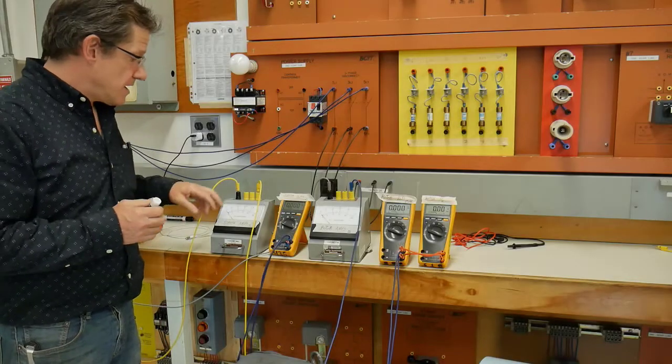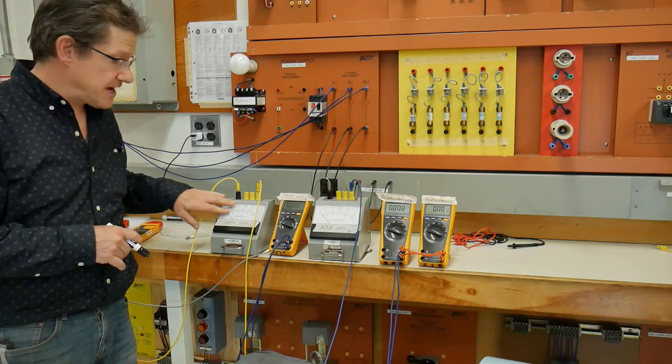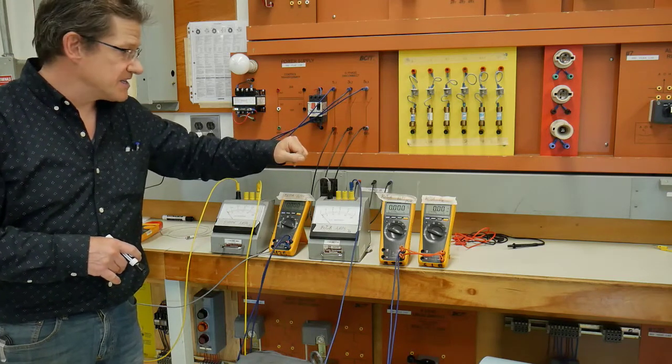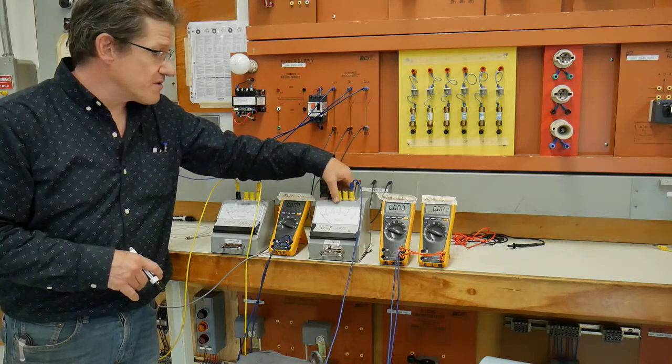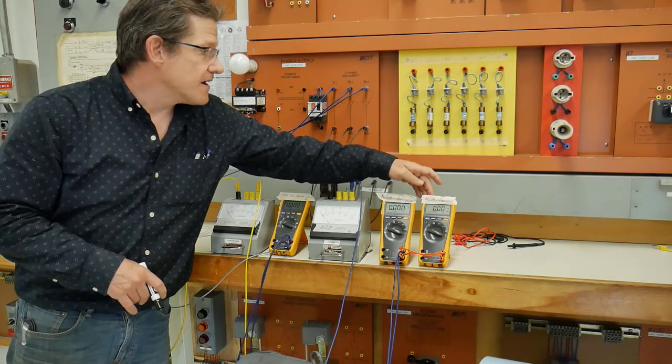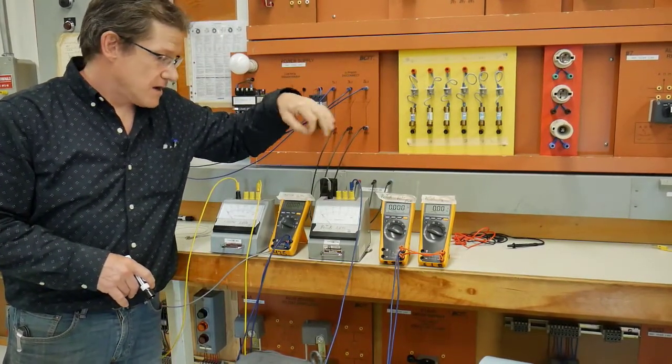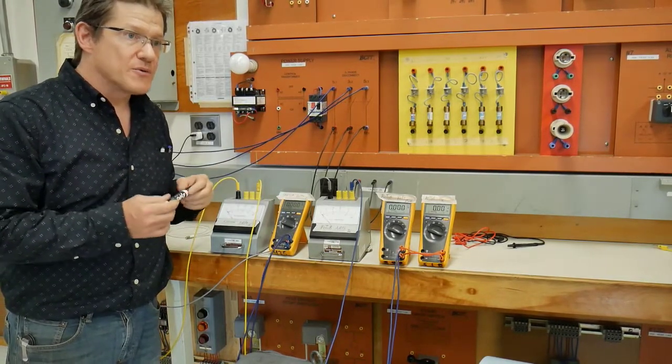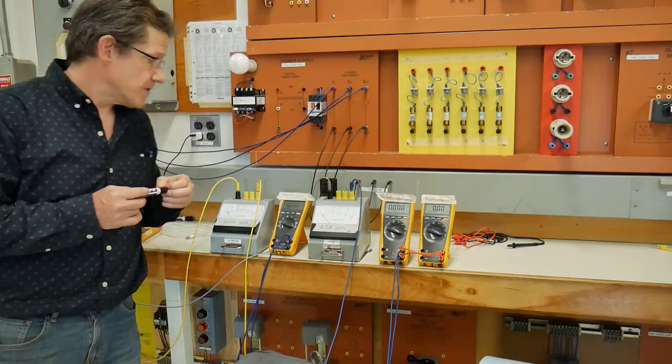Here are our meters all set up. We have an ammeter in series with the stator lines, a voltmeter for stator volts, an ammeter in series with the rotor circuit, and we'll be monitoring rotor volts and rotor frequency. We're going to start the motor with the rotor circuit not connected, so I don't expect any revolution of the rotor yet.